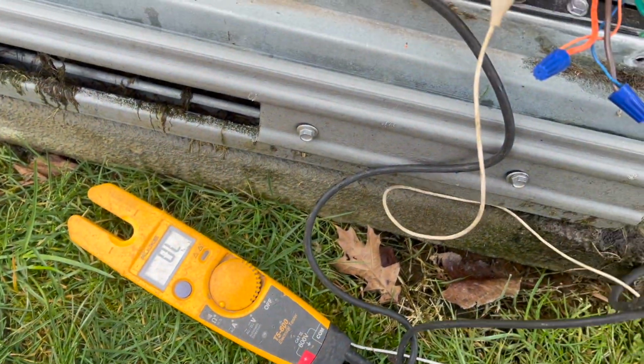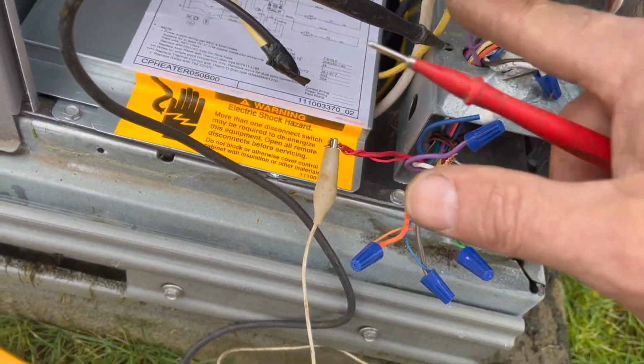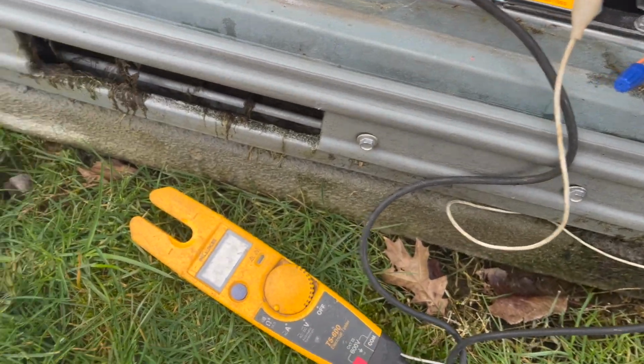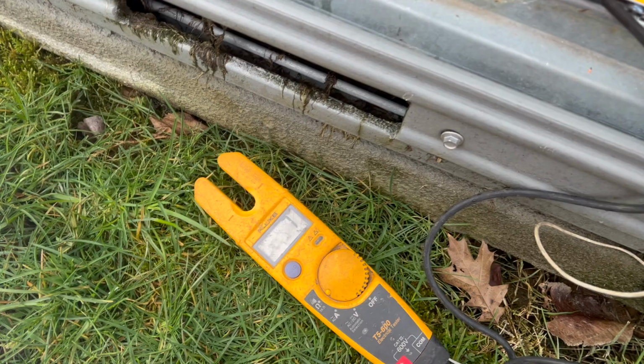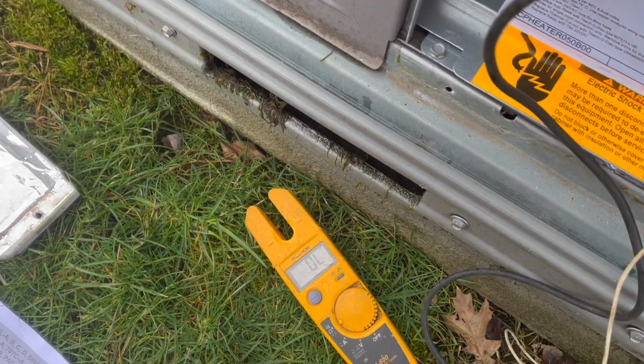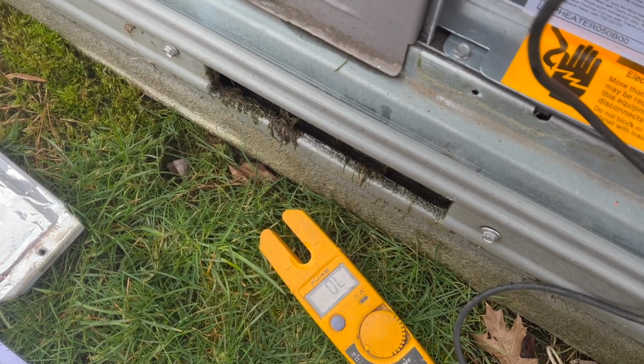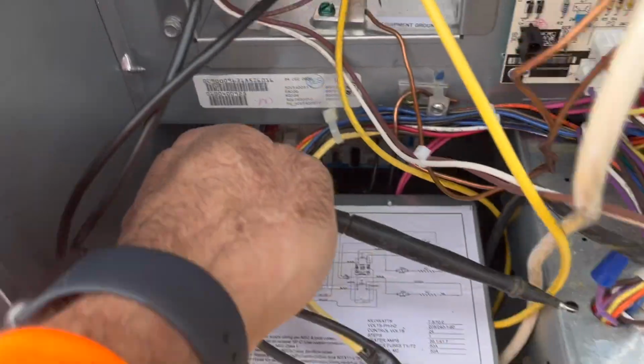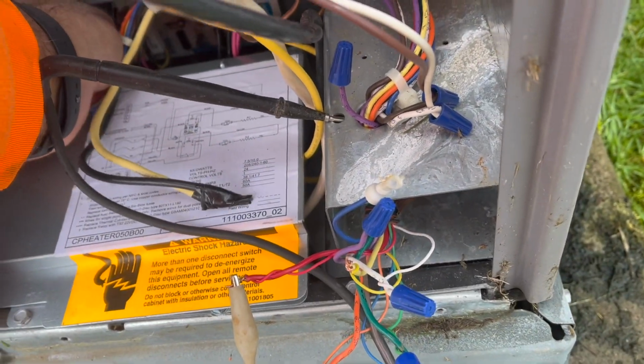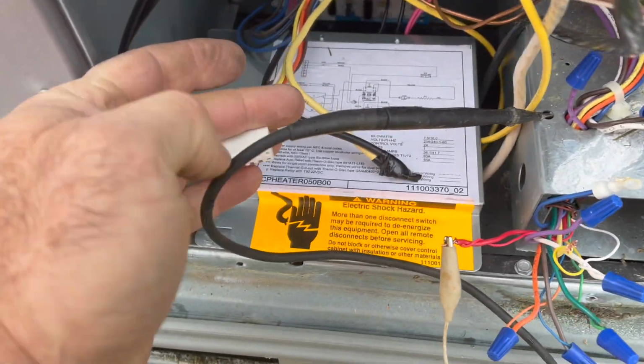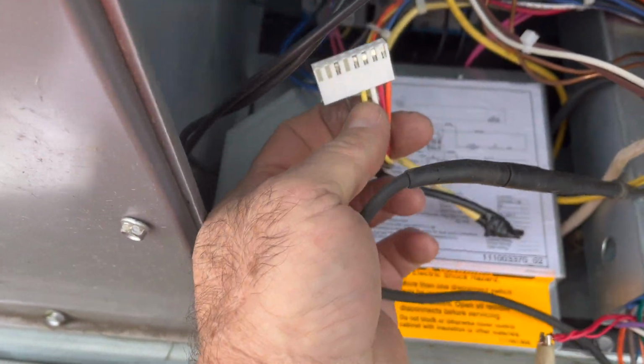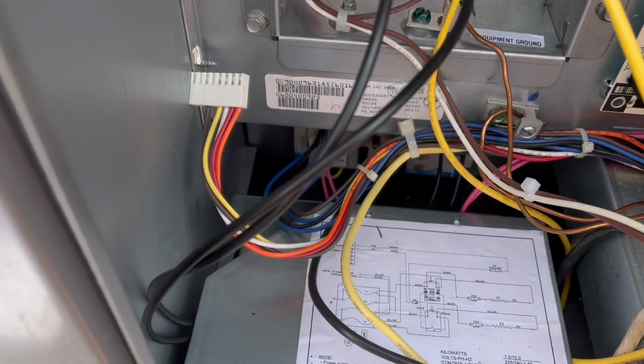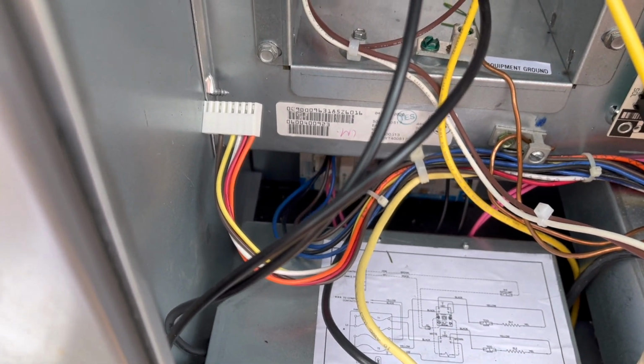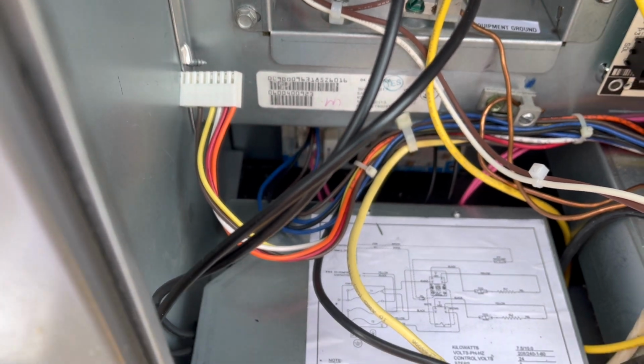Okay, from ground to yellow we have 7 ohms. That's why it lasted a little bit before it blew, but it was still pulling way more than 3 amps. So we've got a defrost board buried down here. There's the wires coming down to it. I just unplugged them and I've got OL, so there's a 7 ohm short somewhere in that defrost board.